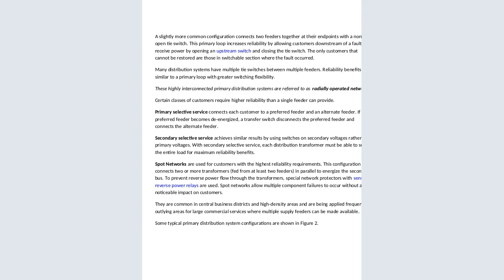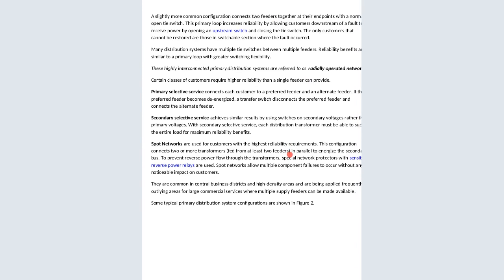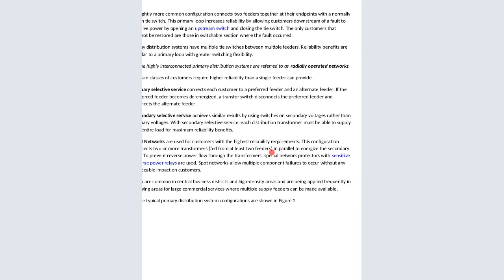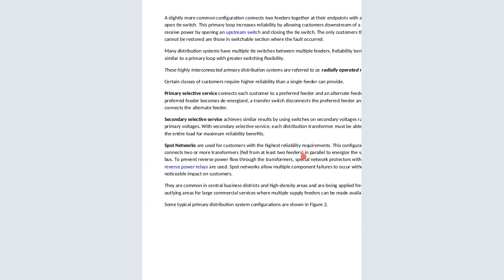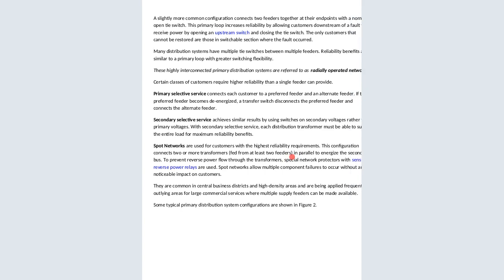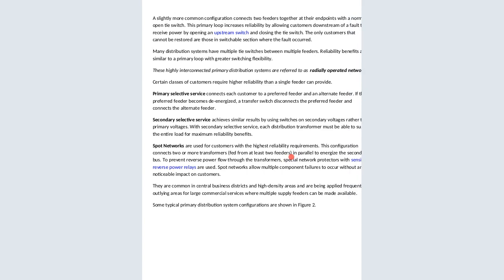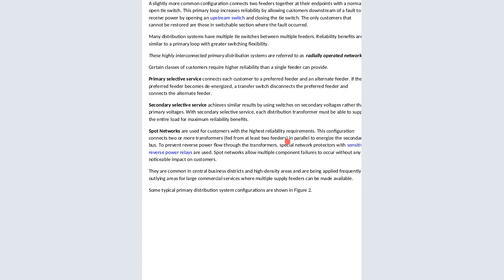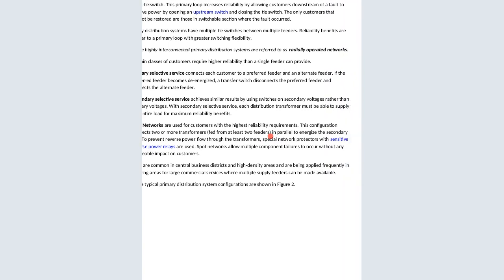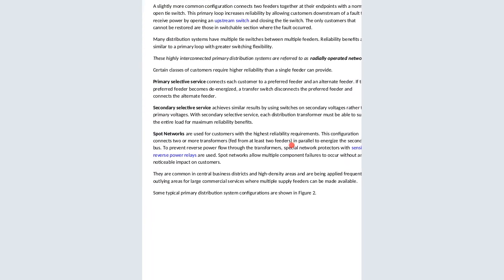So that is now another characteristic of that distribution. Many distribution systems have multiple tie switches between multiple feeders. Reliability benefits are similar to primary loop with greater switching flexibility. These highly interconnected primary distribution systems are referred to as radially open networks, or they're radial.